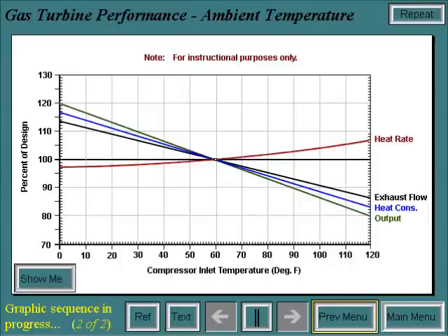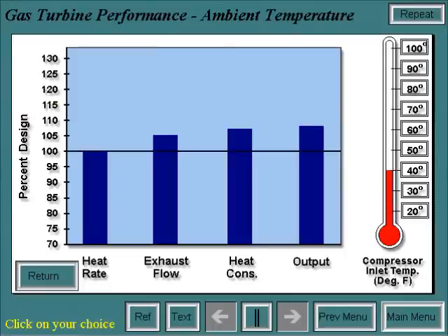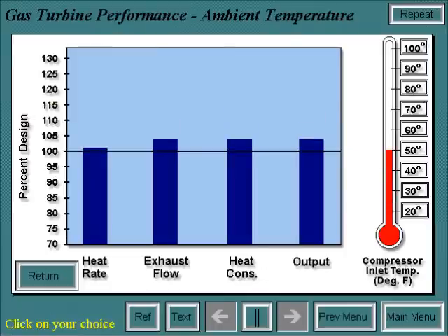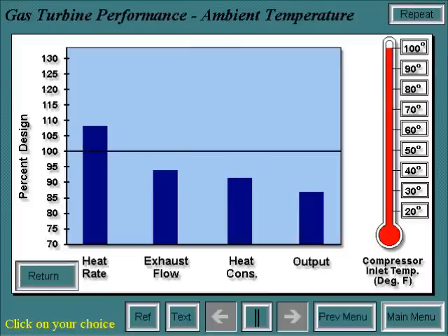Depending on the unit's cycle parameters and component efficiencies, ambient temperature will affect the air mass flow, which in turn will change output, heat consumption, heat rate, and exhaust flow.